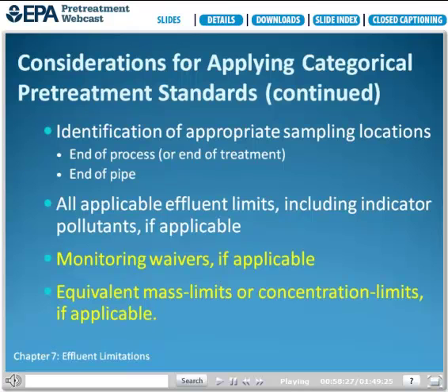The control authority should keep in mind that when the designated sampling location described in the permit contains a categorically regulated waste stream combined with one or more other unregulated waste streams, another sampling point may be more appropriate, such as one at the end of the regulated waste stream, which could only capture regulated waste.